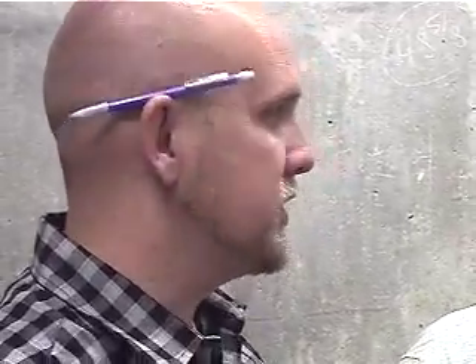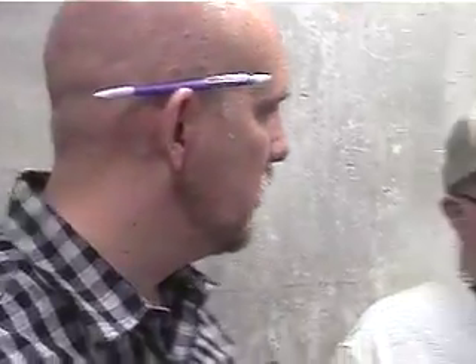One thing big we see here is the pH is wrong. Every seal manufacturer will say you've got to be within a certain pH range. So if on a pump you're finding you're replacing seals a lot, instead of replacing the seal and moving on... A lot of seals we're putting in is due to them being heat pumps, and it's the temperature. Yeah, temperature, absolutely. And that's where we have to play with what seal works the best for that application. So again, pH and temperature are going to affect the seals the most.